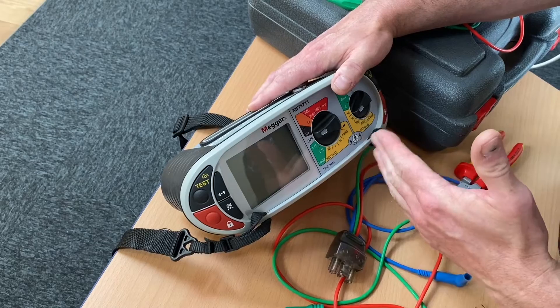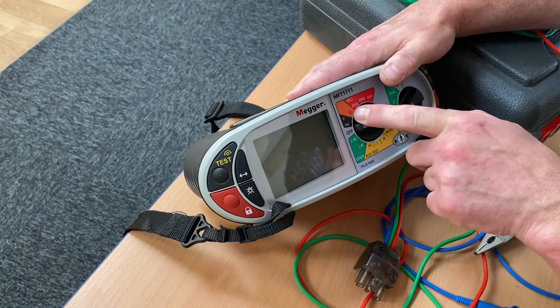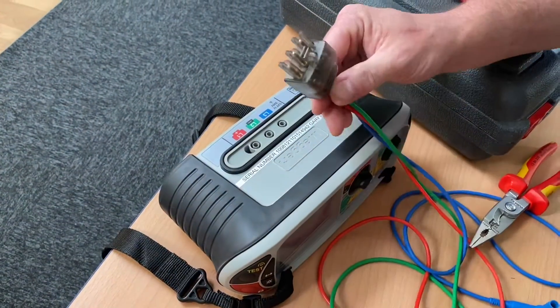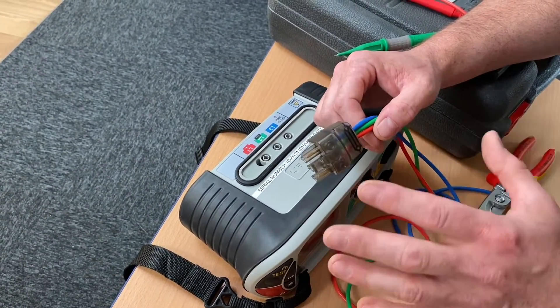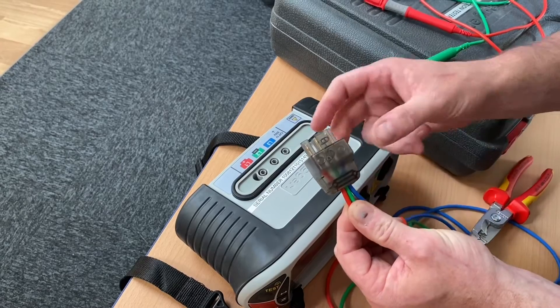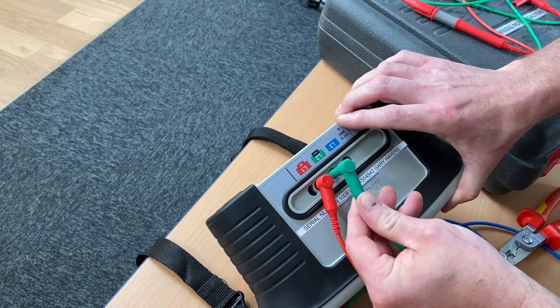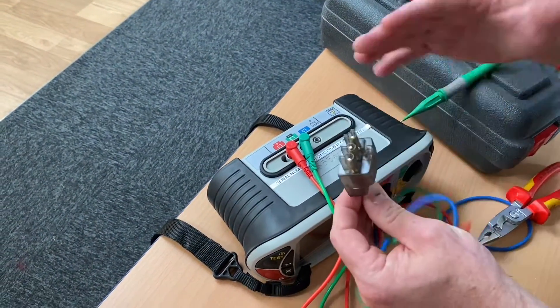We're going to use our Megger MFT to measure the continuity of the CPC. We're measuring resistance, so we go to the omega symbol because we're measuring in ohms. We'll use the red and green leads for the line and CPC. These leads themselves offer resistance, so we need to remove that lead resistance.